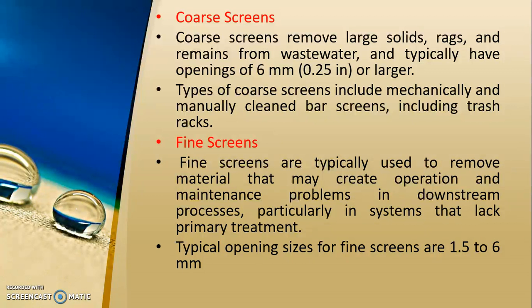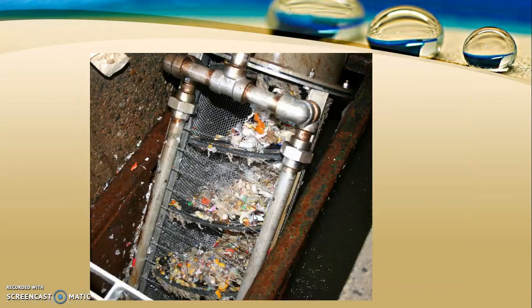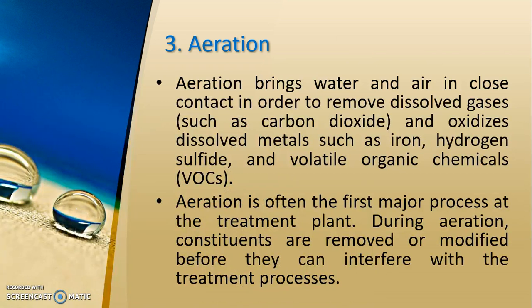Bar screens are also called trash racks. Fine screening is used to remove material that may create operation and maintenance problems in downstream processes, particularly in systems that lack primary treatment. Typical opening sizes for fine screens are smaller — 1.5 to 6 mm — compared to coarse screening. After screening, once the floating matter is removed, water then goes to the aeration process.